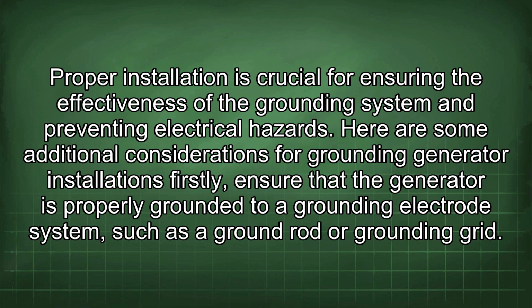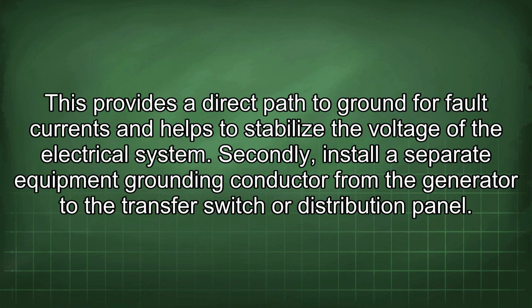Here are some additional considerations for grounding generator installations. Firstly, ensure that the generator is properly grounded to a grounding electrode system, such as a ground rod or grounding grid. This provides a direct path to ground for fault currents and helps to stabilize the voltage of the electrical system. Secondly, install a separate equipment grounding conductor from the generator to the transfer switch or distribution panel.